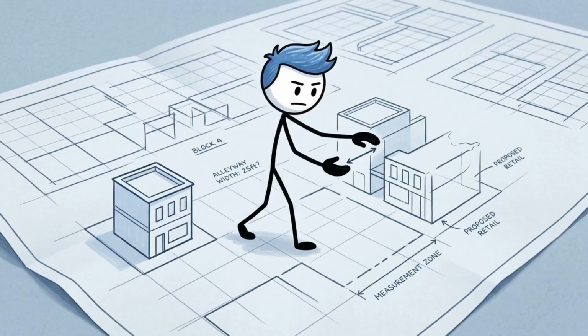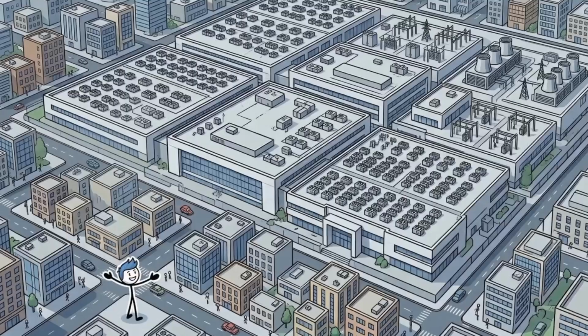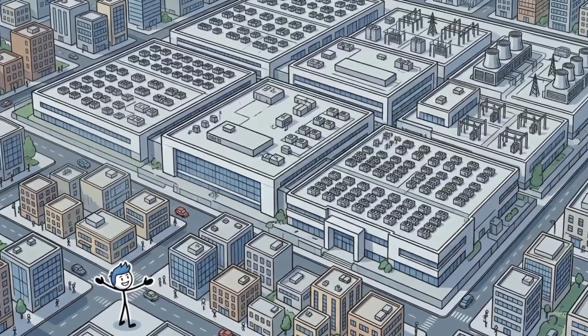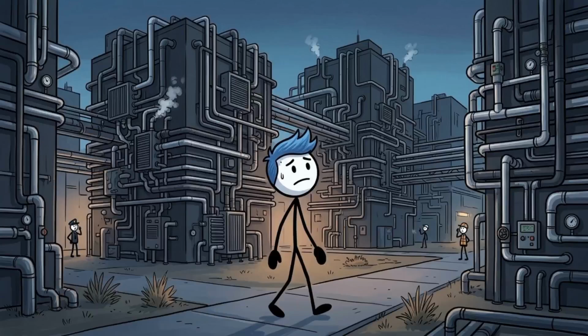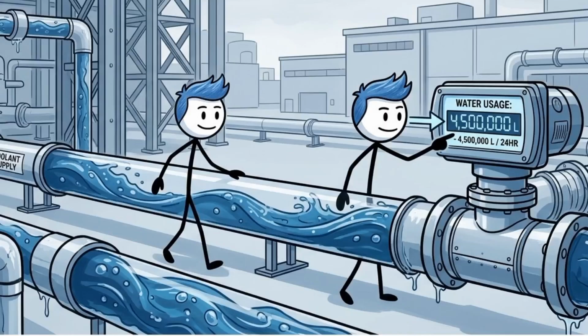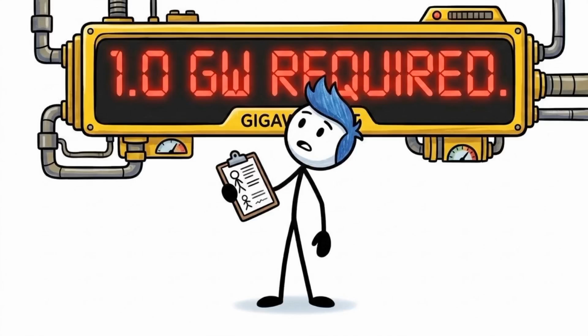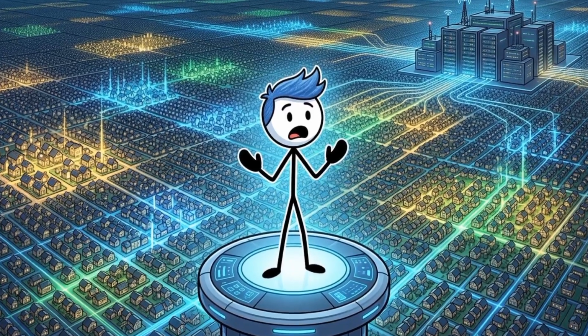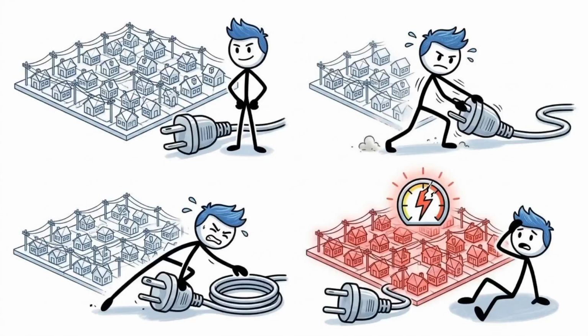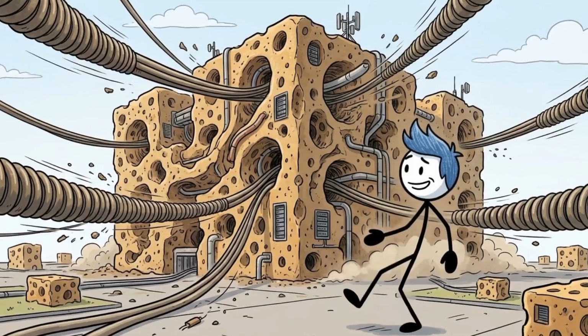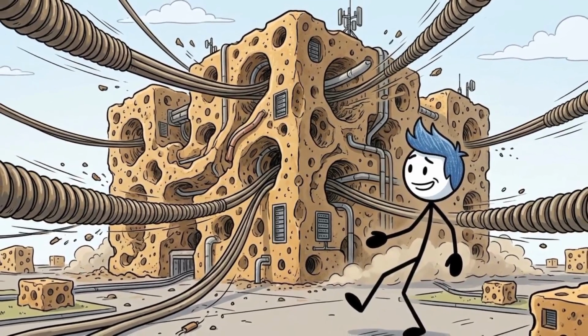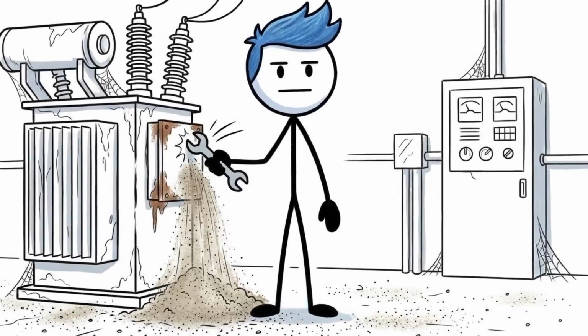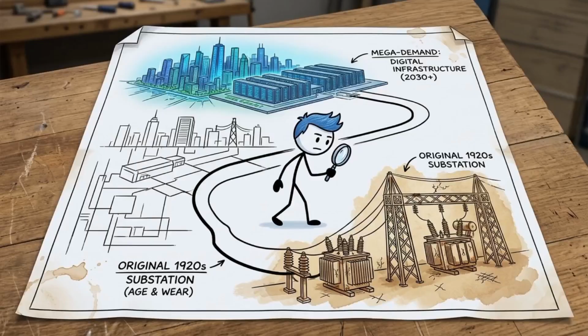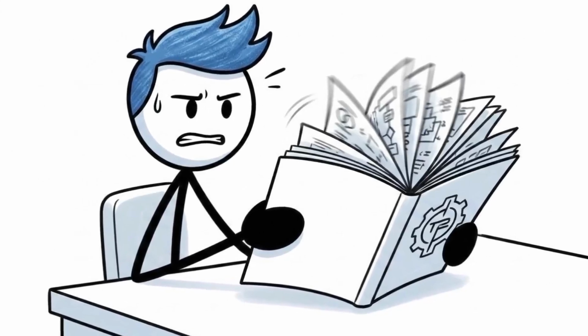But in reality, a modern AI facility isn't just another building on the block. Because of the sheer volume of power needed to run those high-density chips and pump millions of gallons of water through their cooling systems, the largest planned AI campuses can demand up to a gigawatt of electricity. To put that in perspective, that is enough power to support roughly 750,000 homes. And they are trying to hook these massive thermodynamic sponges up to an electrical grid that was largely designed in the mid-20th century. Which brings us to a beautiful piece of operational absurdity.